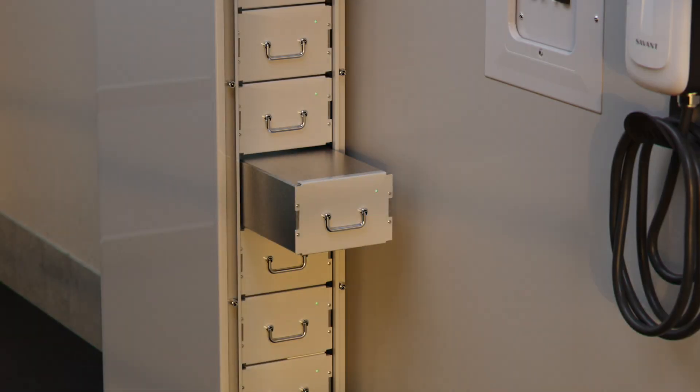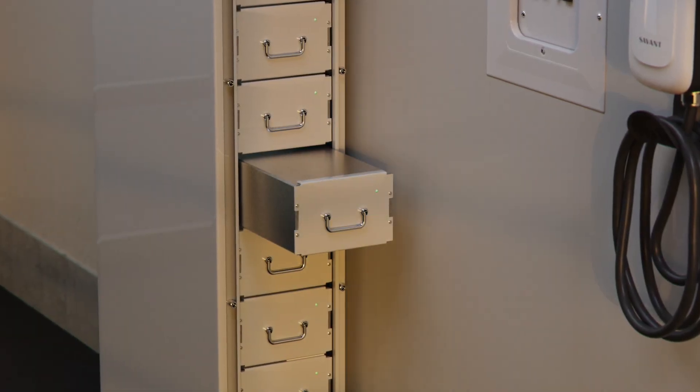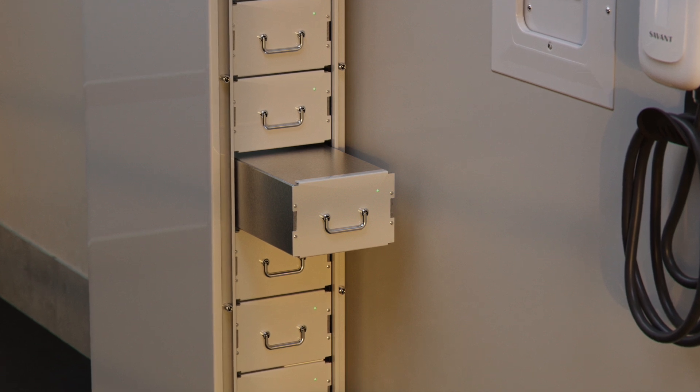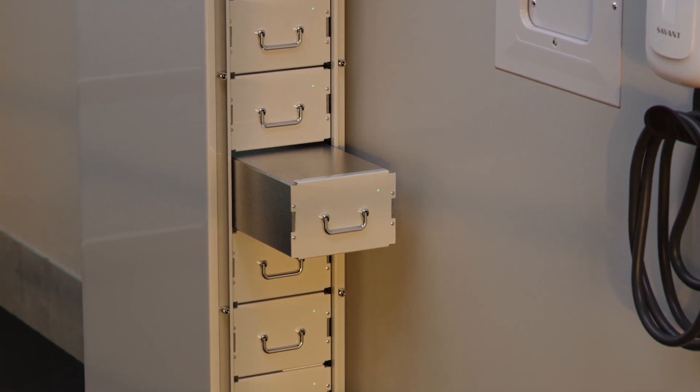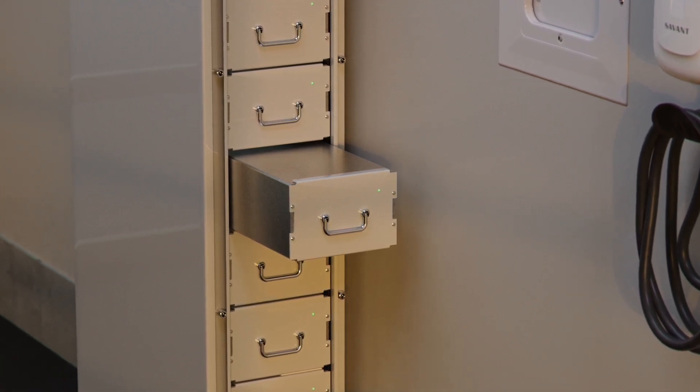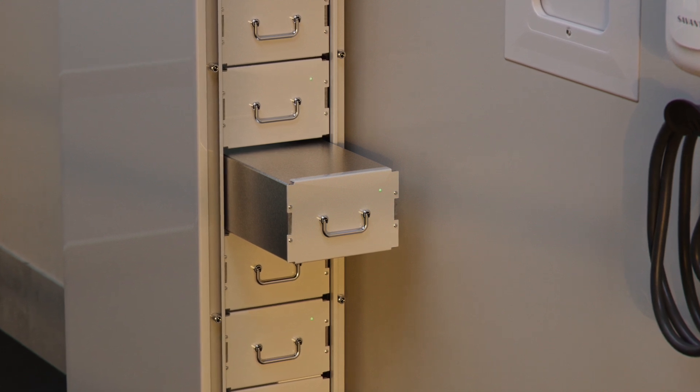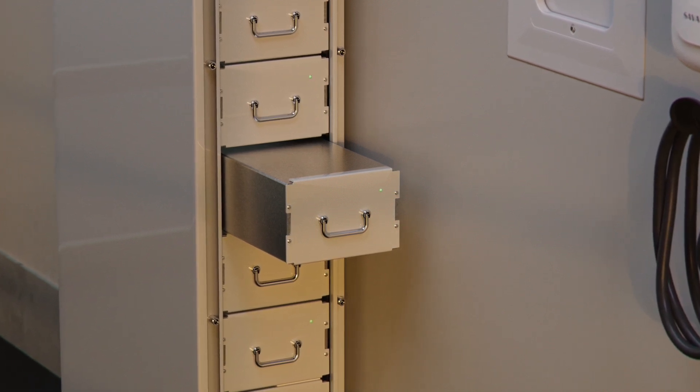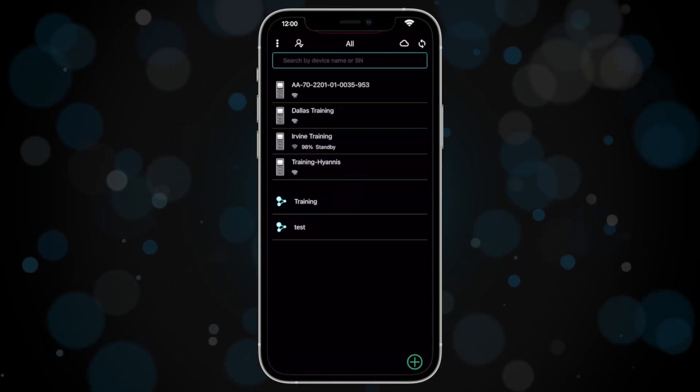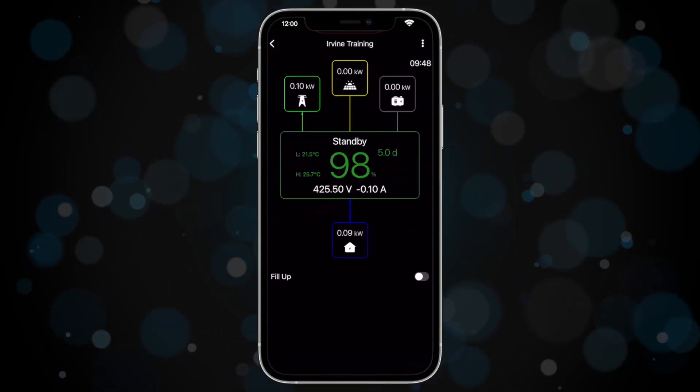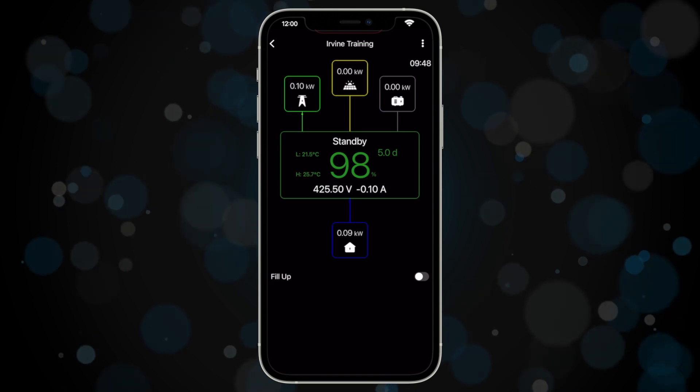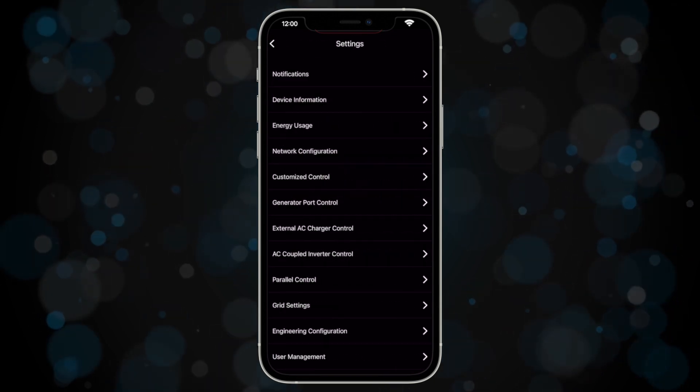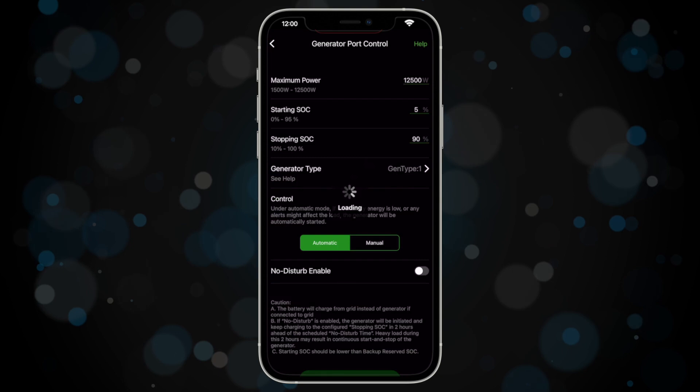Once all connections are made and you've completed the proper startup sequence of each Savant power inverter, refer to our startup sequence guide for more details on that process. You'll need to configure the generator port for proper generator control. Start by opening the Savant power storage app, connect to the primary unit, open the settings menu by tapping the three dots button in the upper right corner, and navigate to the generator port control screen.